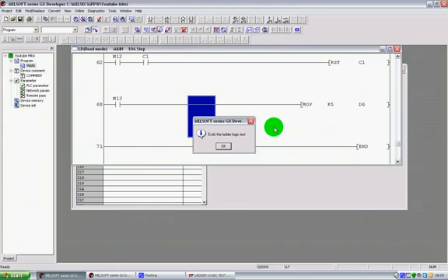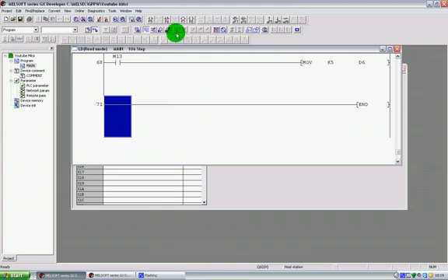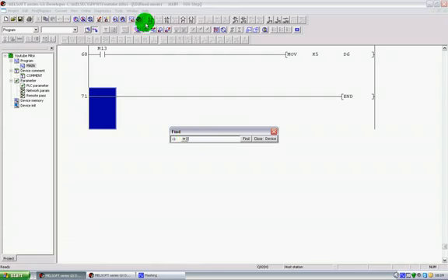Again, you've got to be a little bit careful with these values and these moves, especially if you're using contacts like this, because of course you may be making this line true constantly. Now if this happens to be another data register, then if one value keeps changing, then it will change the other one. So sometimes you may only want to put the value in on a pulse.